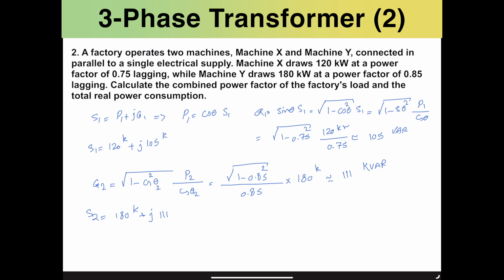That's the total power considered in our case. We need to be mindful that the reactive powers are positive here, since we're dealing with a lagging system and they are inductive. In a lagging system, dealing mostly with inductive circuits, the current actually lags the voltage, and that's why we have positive reactive power, so Q becomes positive. Conversely, Q becomes negative for leading circuits that use capacitors.